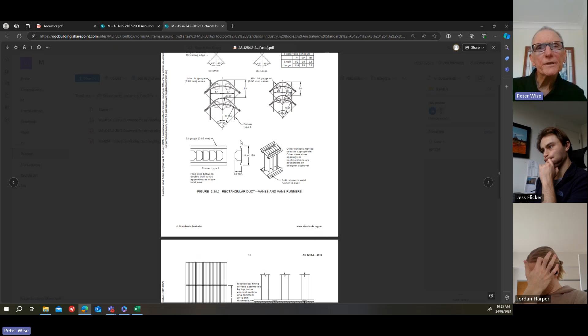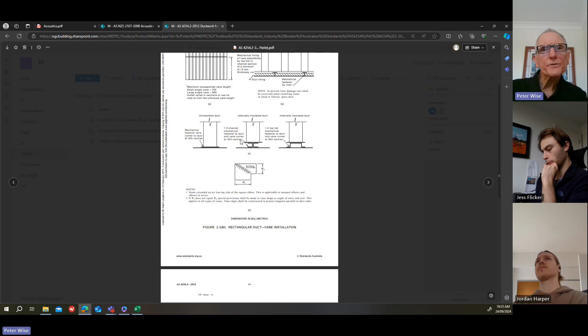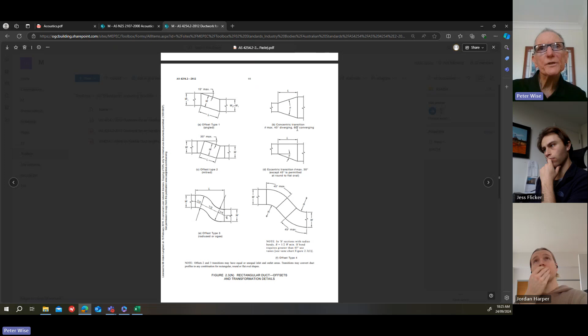The Air Duct guide as well - I can't think what number it is, but in the DA guides there's one volume on ductwork if you're looking for information on how to design duct. This gives some information on offsets: 15 degrees maximum for an included angle on a concentric transition, maximum 45 degrees, diverging 60 degrees, and so on. That information is available if you want something to refer to.